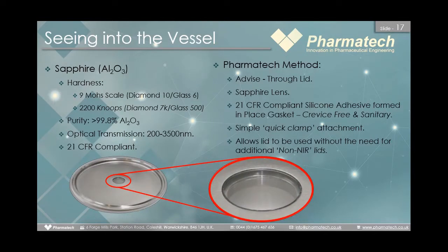Throughout the last few slides, I've kept talking about it seeing into the vessel. How do we do this? We fit a sapphire window, which is considerably harder than glass, but not quite as hard as diamond. We select sapphire because of its optical transmission. It's a 21 CFR compliant material. The way we mount this is that we'll effectively bed it into a food grade silicone adhesive, which is a formed in place gasket. It gives you a completely smooth internal surface. So if you aren't using NIR, the lid can be used for normal tumble blending.